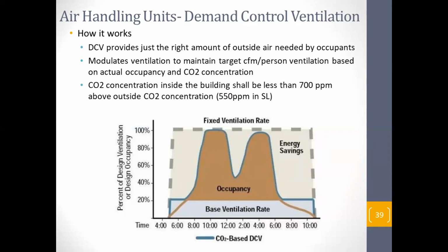So the Sri Lanka current standard is 1250. That is 550 at the intake and 700 addition within the premises. So 550 plus 700 goes to 1250. That is the limit. When you hit 1250, you can start opening the ventilation. When it is less than that, you can close it. For which you need to have a VAV system for your ventilation.